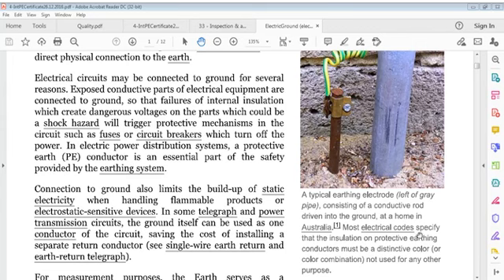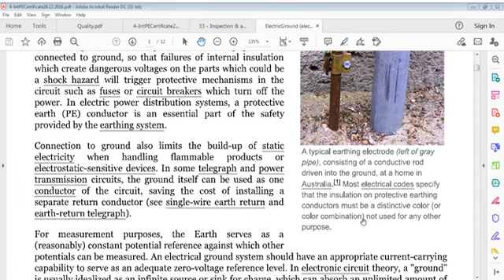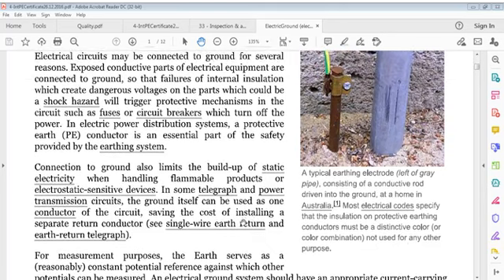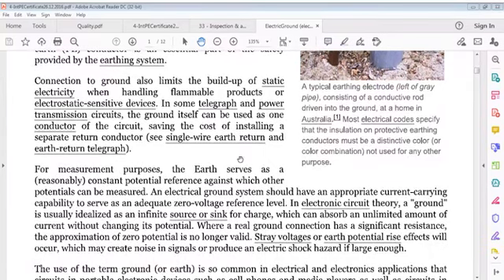Most electrical codes specify that insulation on protective earthing, that's PE conductors, must be a distinctive color or color combination not used for any other purpose. Okay, now we say connection to ground.